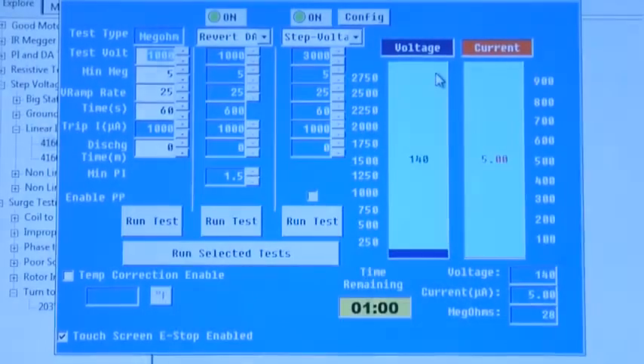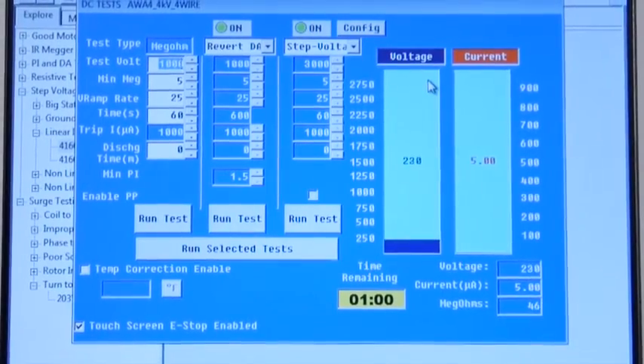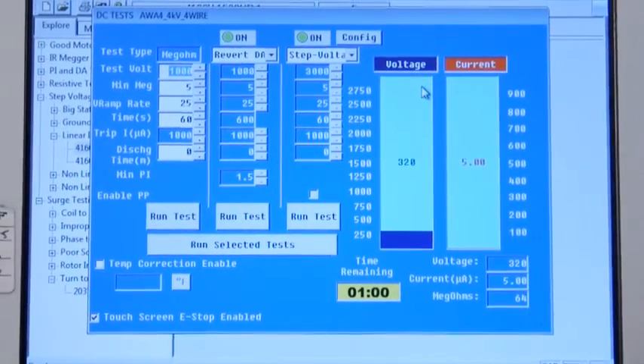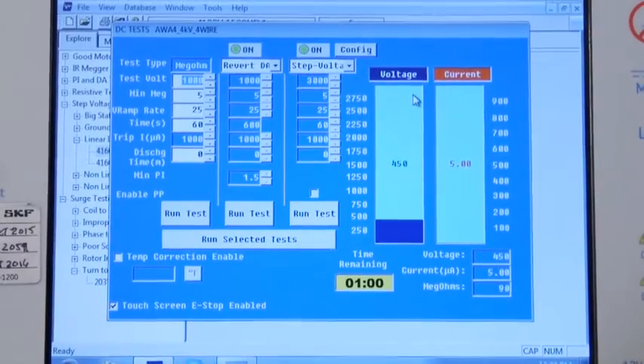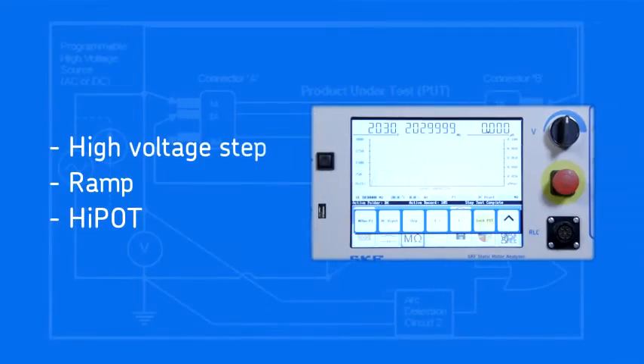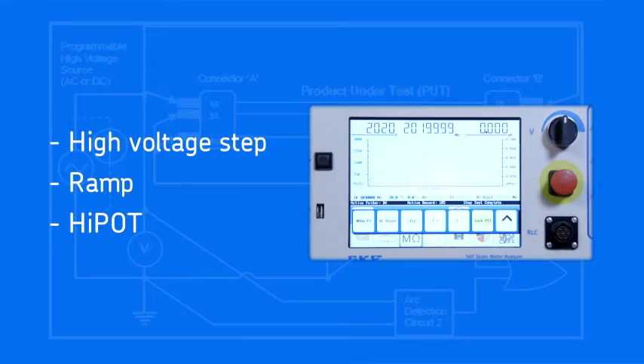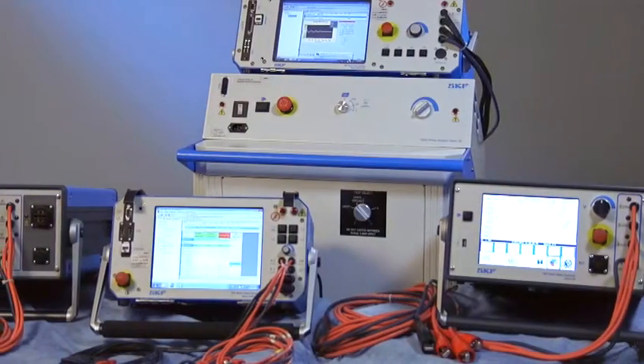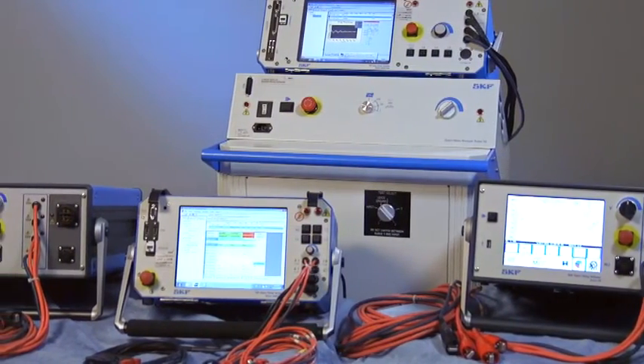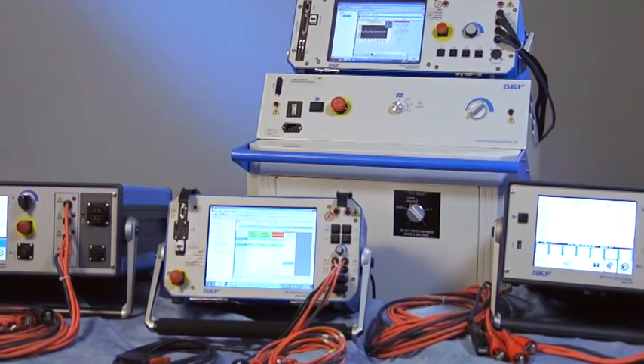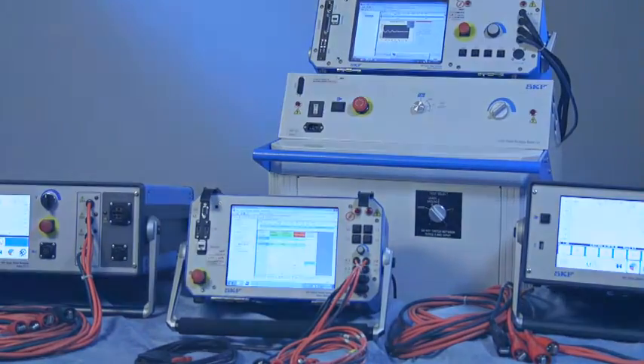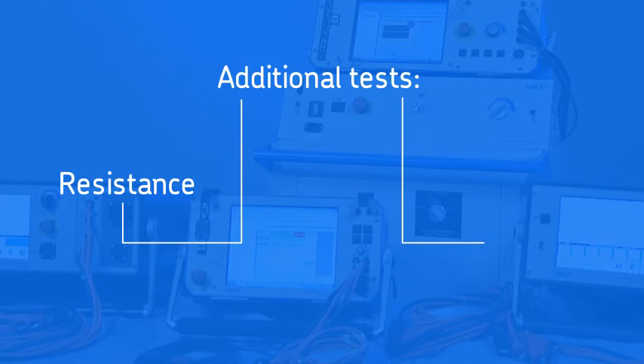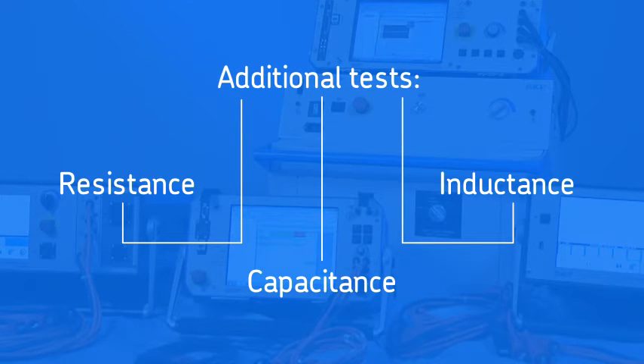Ground wall testing is done with a meg-ohm test, but meg-ohm test alone is an incomplete test of ground wall insulation. To completely test the ground wall insulation, high voltage step, ramp, and high pot tests are also used. SKF static motor tests are non-destructive and follow IEEE and IEC motor testing standards for motor insulation testing. Additional tests available include resistance, inductance, and capacitance for verification of motor winding construction.